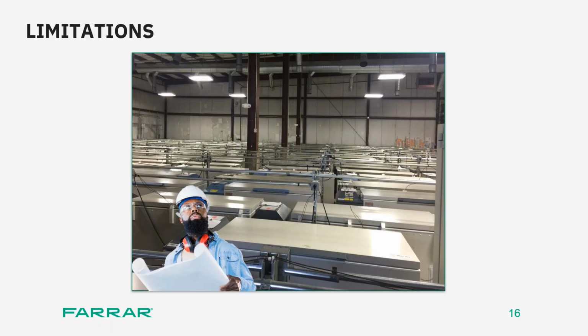So remember this, although you have an available footprint for additional freezers, there may not be enough capacity to remove heat from the space. And if this isn't taken into consideration, this can affect all of the freezers that you have. It could be affected by poor performance due to the compounding heat, which can inevitably lead to early failure and, of course, spoiled product.